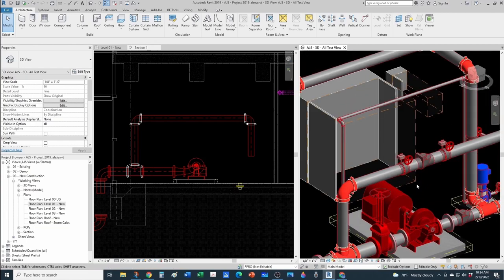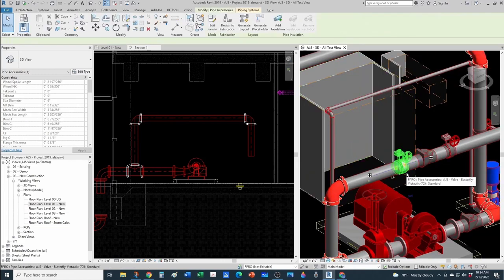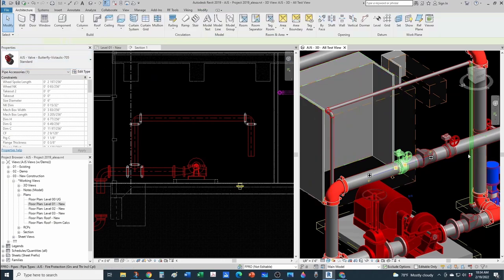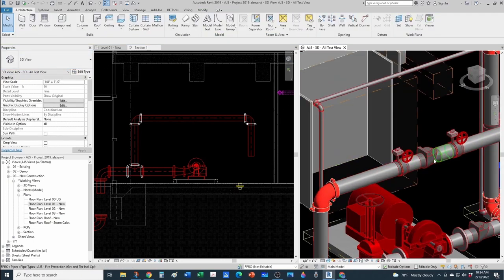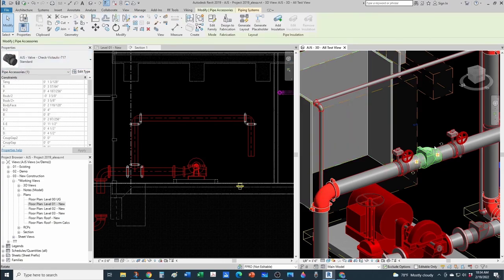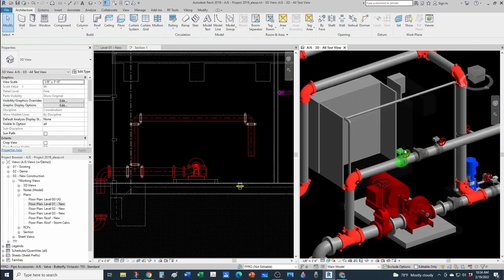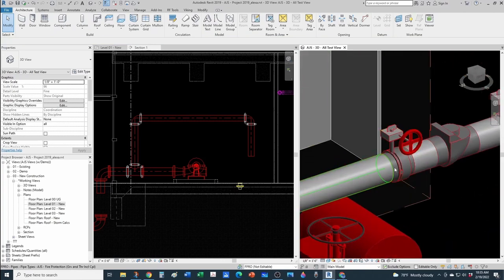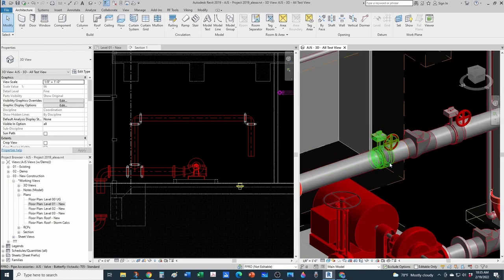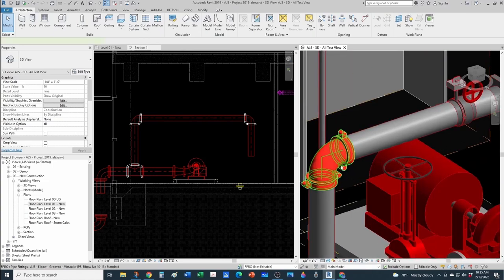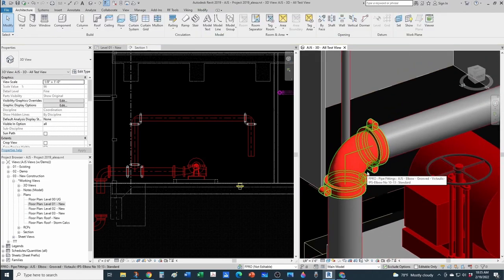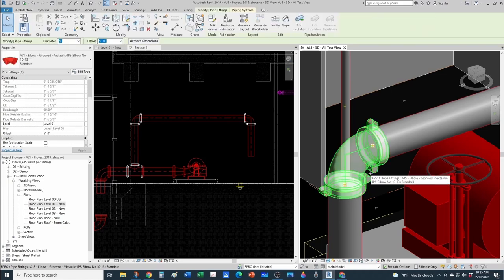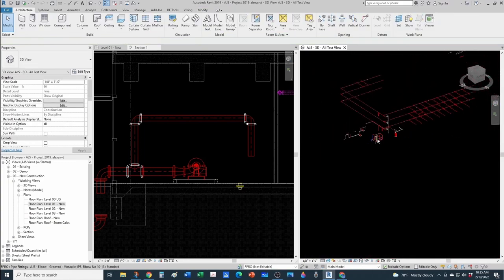A good valve that I use, I'm a big fan of Victaulic. So my valves are typically Victaulic. So this is the 705W, which is a butterfly valve, and this is the 717, which is that check valve, right? And the reason you're not seeing the groove couplings here is because this family itself doesn't have the grooved couplings contained like my elbows. What I did with my elbows is that I have the generic elbow that comes from Victaulic, and then I nest the couplings into it so that it's a little bit easier for me.